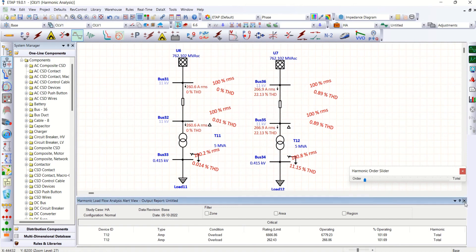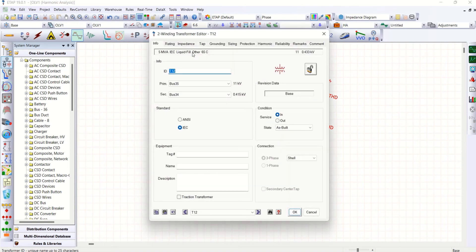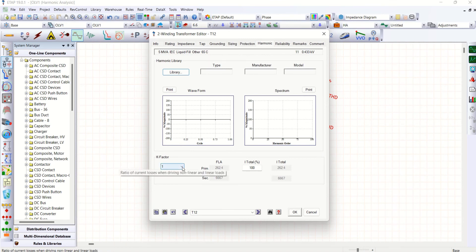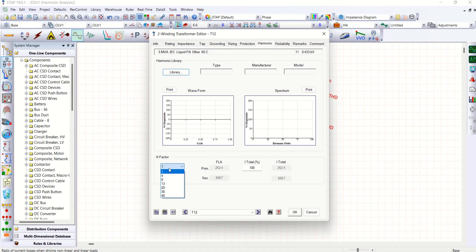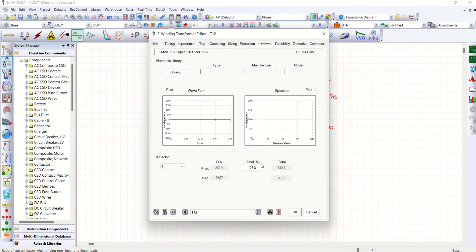Now we go to this harmonic page. Here you see K factor. K factor. You can use any one of this case. K1 means normal as like standard transformer. K4 means you look at actual full load current of the transformer is 262. But when we use K factor as 4, it is handling up to 330.1 amps. That is 125.8 percent of your full load current, both in primary as well as secondary. You could see here.